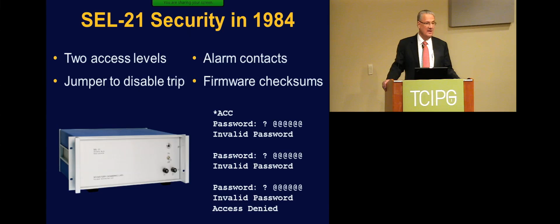So we said, if we're going to hook stuff up to a phone line, that was the way to do it then, we got to make sure that we put some security. So I said, we're going to do 2 levels of access control. So if you get right on the serial port on the back of this and you send carriage returns to it, you get a splat for a response. And if you put in the command access, ACC on the screen here, then it'll come back and prompt you for a password. And even then we used all printable ASCII characters. So case was important, and you could use anything on the keyboard and then some. So if you got it wrong, it would give you 2 more tries. If you got it wrong 3 times in a row, it would bang the alarm contact. So then you had an independent means of knowing if somebody was running passwords.